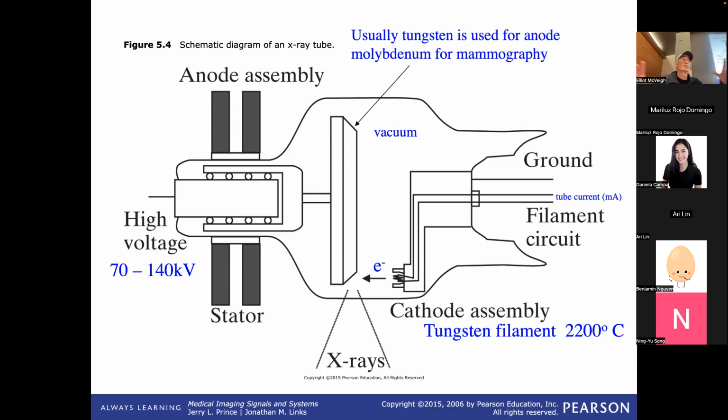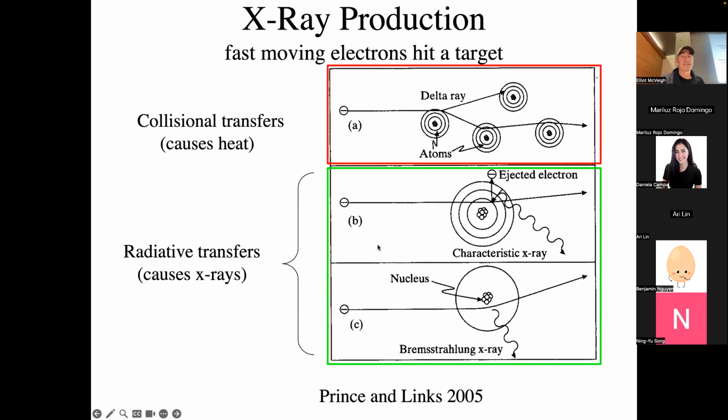So that means these tubes have become more powerful, more powerful, more powerful over time. And they've become way more expensive over time. So if you blow one of these tubes, you know, it's maybe 100 grand for that light bulb, right? Or more. And that's why you have these service contracts on these machines, because eventually you blow one.